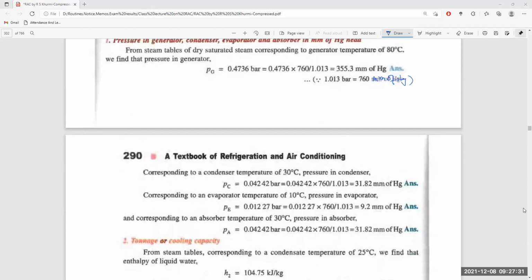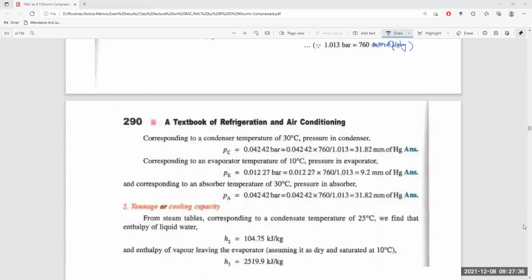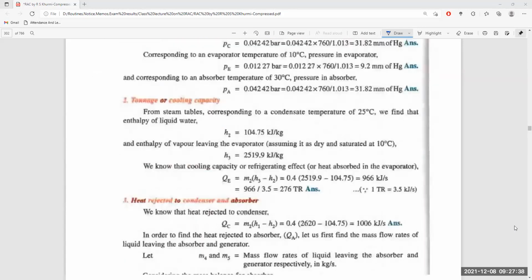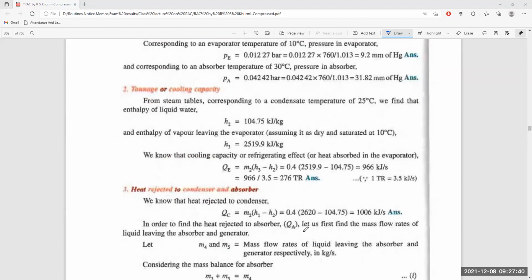Corresponding to the absorber temperature, this is the cooling table. Then the heat rejected to the condenser, QC, is the mass flow times H1 minus H2, given as 2620 minus 104. That is the enthalpy of the vapor coming into the condenser minus the enthalpy going out. That is 2620 minus 104.75, which is 1006 kilojoule per second.